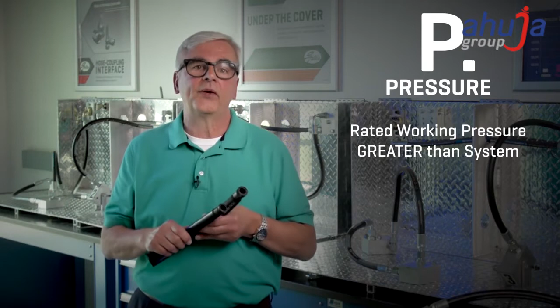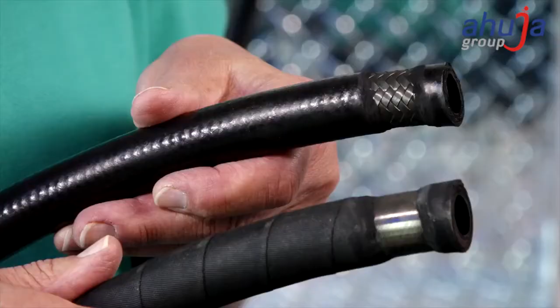The P stands for pressure. Make sure that the hose has a rated working pressure that is greater than the system it's going to work on. In addition, you want to make sure that you select the correct reinforcement. If you cut a little bit of the hose cover off the hose you're looking to replace, you'll be able to see if it's wire braid or spiral.